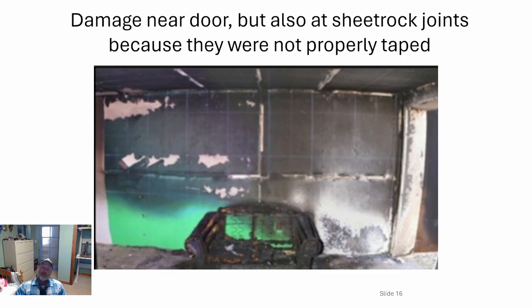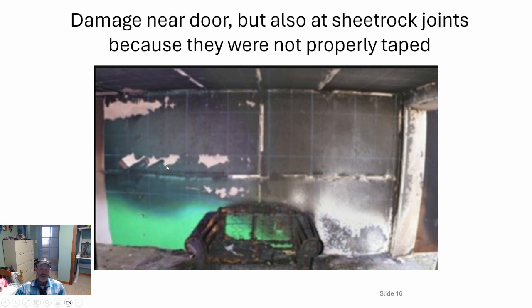Here's another interesting example of this geometry effect. You had this love seat with the door open and clean burn — so a lot of ventilation coming in right here, a very hot fire here. But on the other side, nothing — it didn't burn the paint. This image also illustrates taping marks on the sheetrock seams, showing ventilation associated with those seams. It demonstrates why adequate taping is so important for fire-rated construction and why inspection is required before issuing a certificate of occupancy.